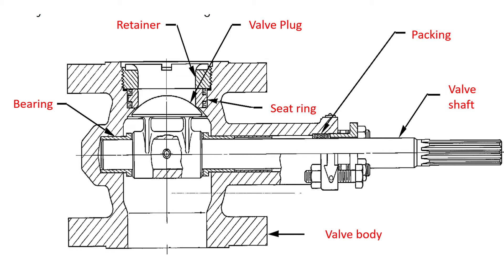Trim refers to the valve plug, seat, and internal surfaces of the valve body. The seat ring meets with the valve plug, and the main application of the seat ring is to provide a complete shut-off when the valve is in the closed position. The retainer — as the word itself suggests — locates and secures the seal or seat ring in the valve body, protecting and securing it in place.